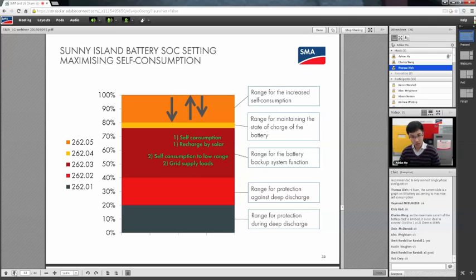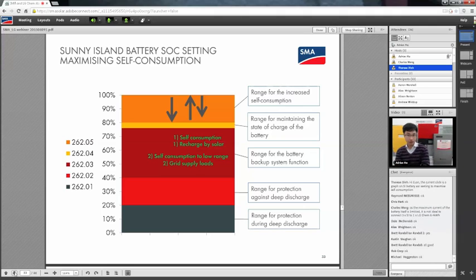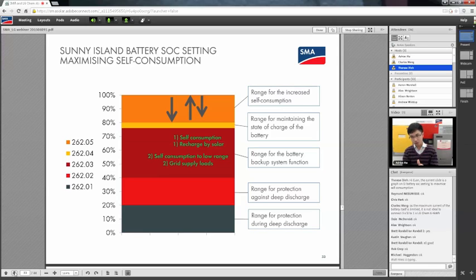Scenario 2 is when we have a thunderstorm and the loads are quite large, or after a few days, the battery state of charge hits our first range there, 80%. Once the battery state of charge hits the 80% mark, the battery will stop supplying the loads. All the rest is supplied by the electricity grid, plus the solar, if you have some.